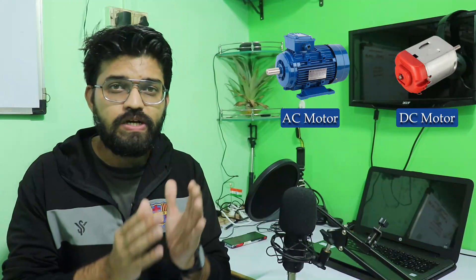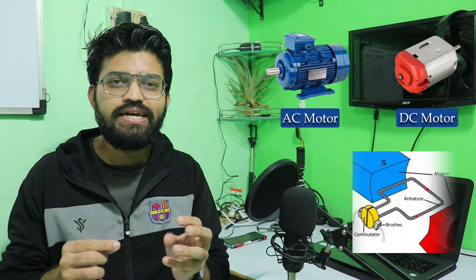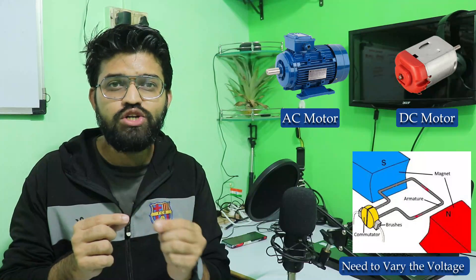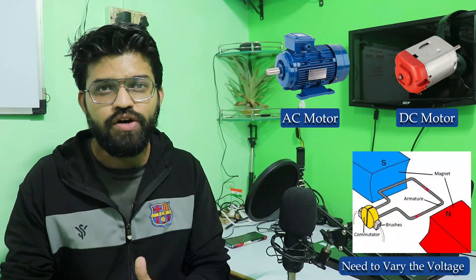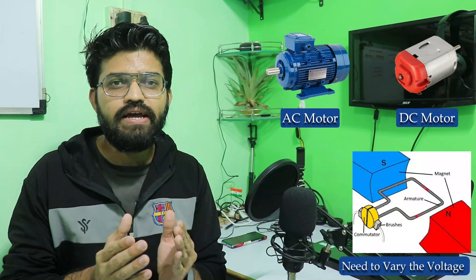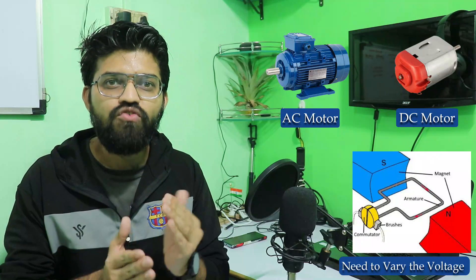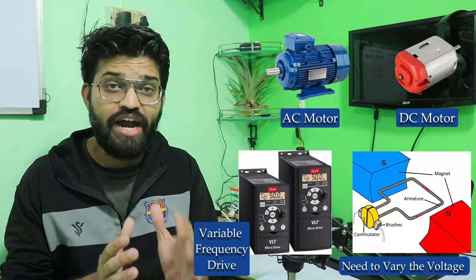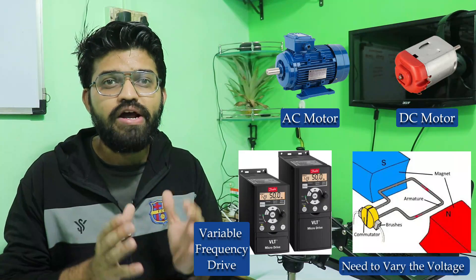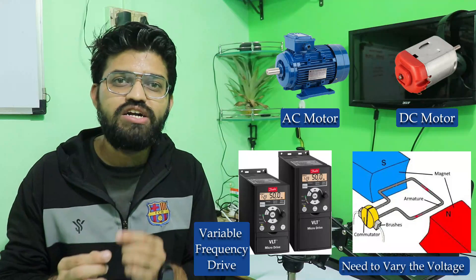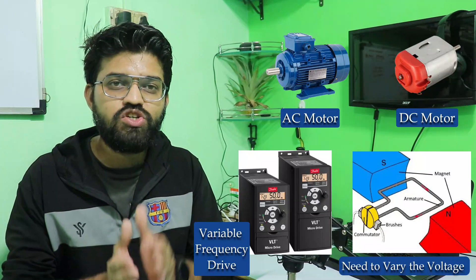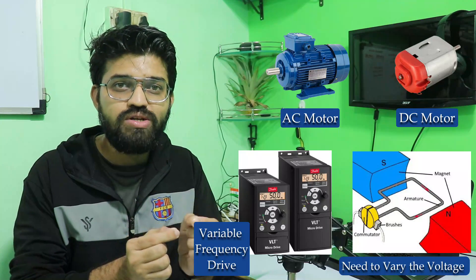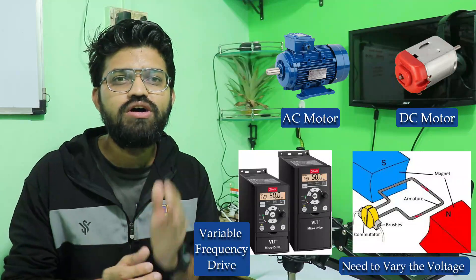For speed control, to vary the speed of a DC motor we need to vary the current flowing through the armature coil. In the case of the AC motor, to regulate the speed we use a VFD — variable frequency drive — by altering the frequency of the alternating current passing through the stator windings. By using a variable frequency drive we can vary the speed of the AC motor.